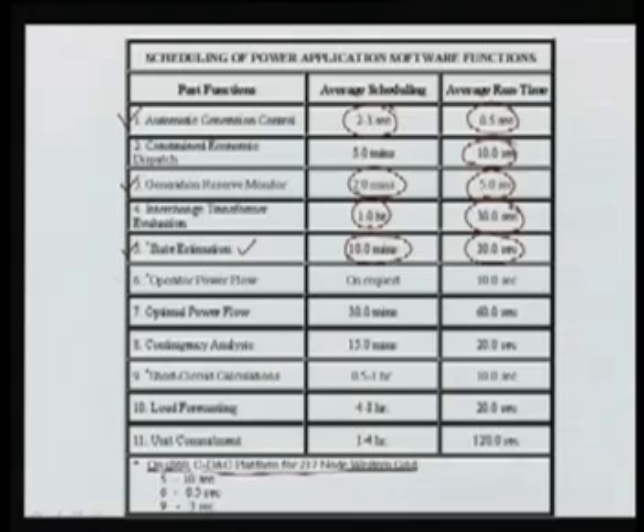Another function is operator power flow. It is normally done on a request basis. If it is required, then only it is done, but its computational time requires at least 10 seconds. That is CPU time. There is no elapsed time here; it is the computational time. So it is the operator's power flow, which is done whenever it is required, that is, whenever it is asked for, and then it is done.